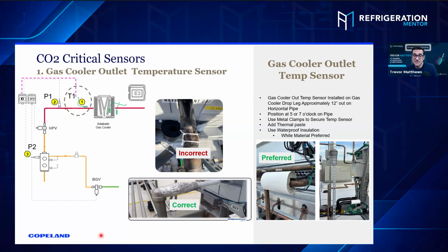the manufacturer recommends. One of the things when you're operating transcritical and the fans are at full speed, they're full speed. It's when the fans start to modulate and you have airflow that the T1 temperature sensor is changing temperature all the time. So you want it to be as accurate as possible, because you've got a saturated condition that you're also dealing with in a subcooling set point. So the more accurate you can make it, the smoother the performance will be.